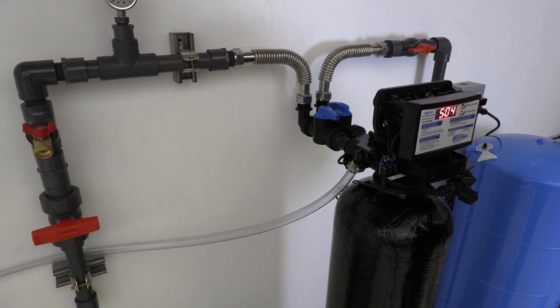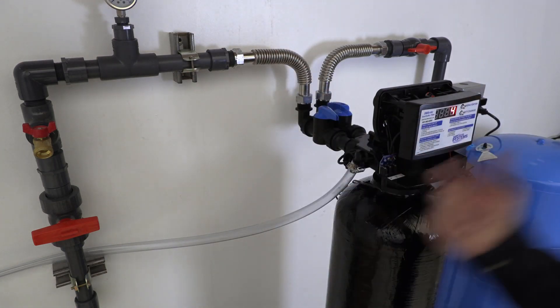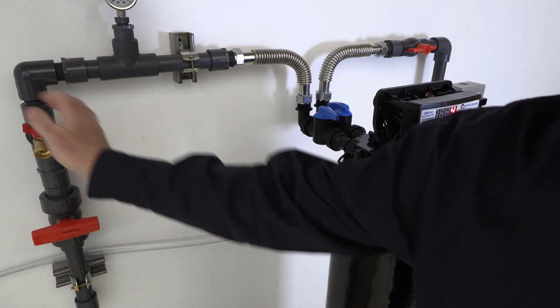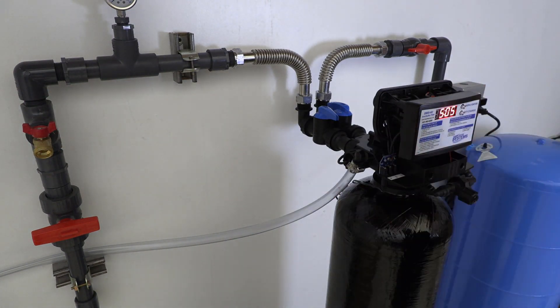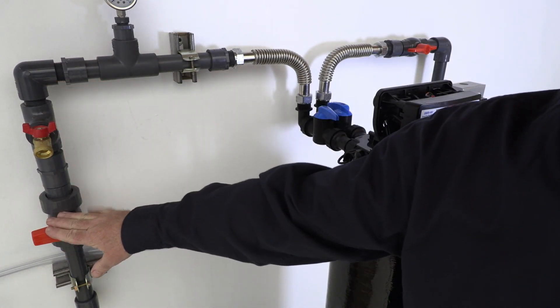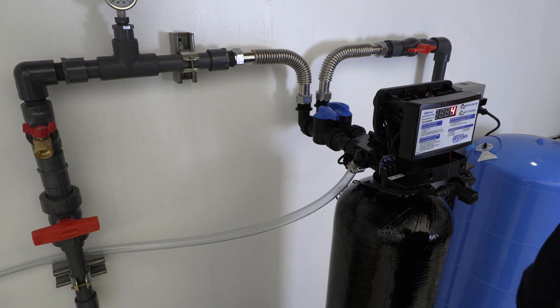Again, once you go through your backwash and rapid rinse, go ahead and sample here again. Take a look, see the clarity of the water. You just want to keep repeating that several times until you see some clear water coming through here in your service position. Again, you still want to keep the house isolated. And if you had any other appliances here—water softeners, additional filters, UV units, reverse osmosis, anything like that—you want to have those isolated until you're seeing this clear water come through here.